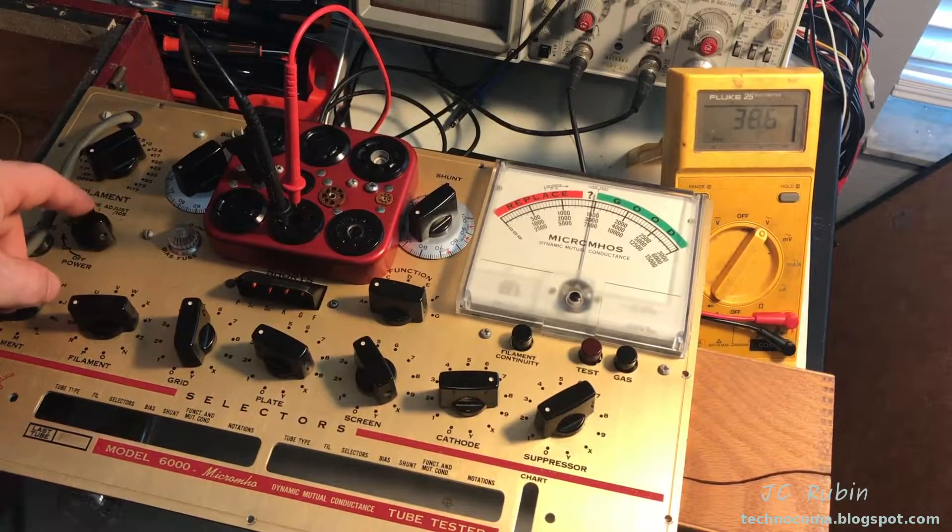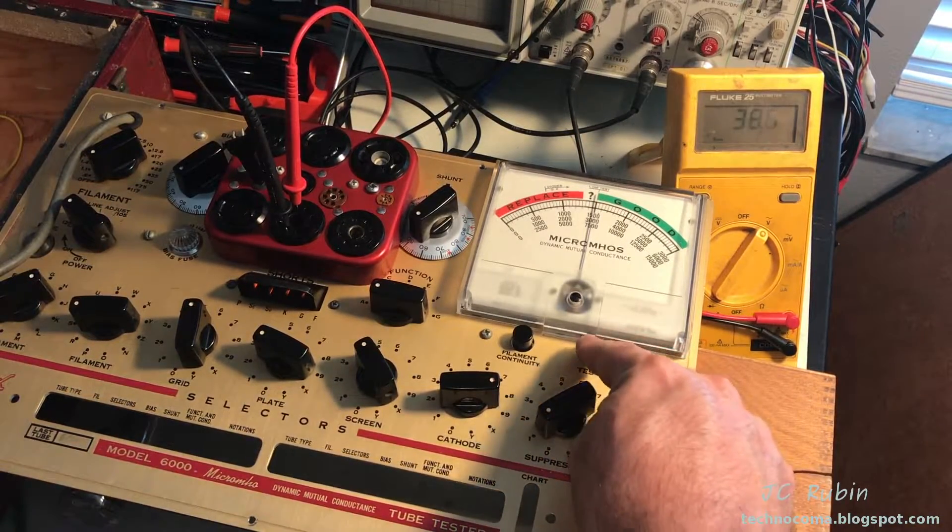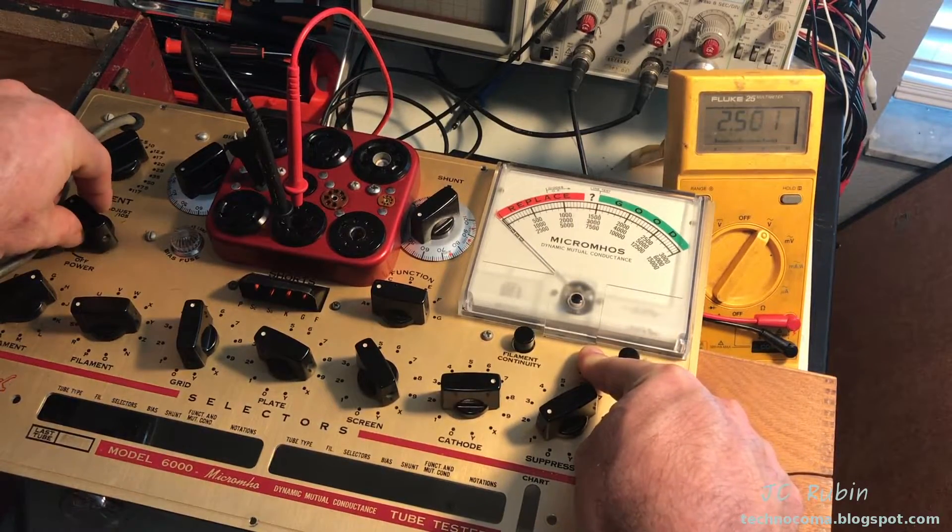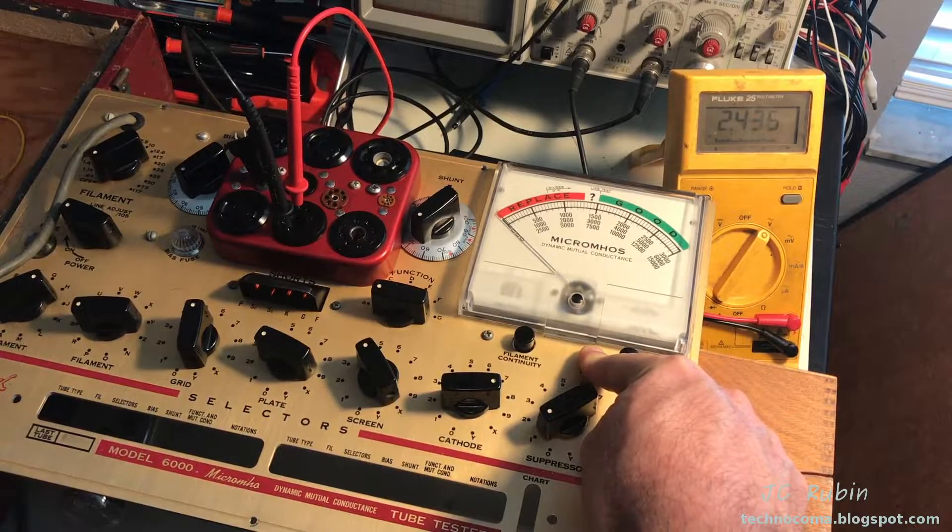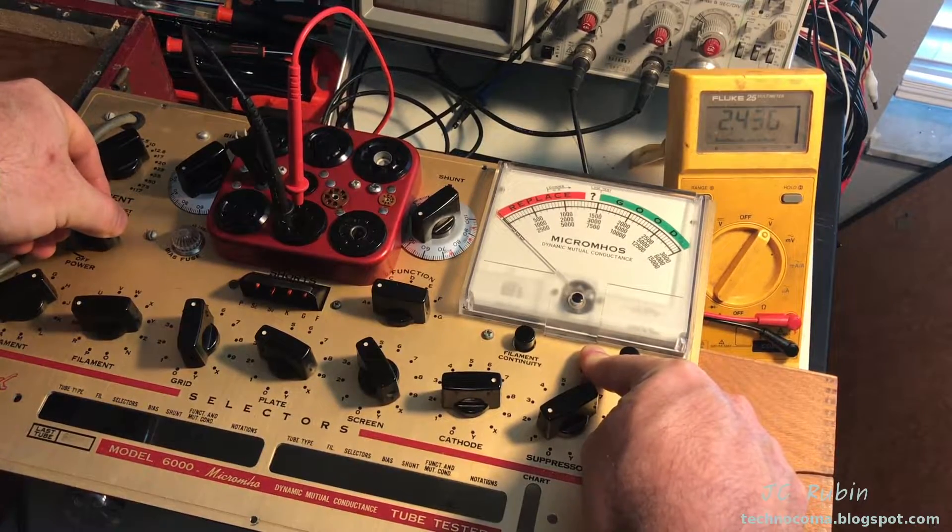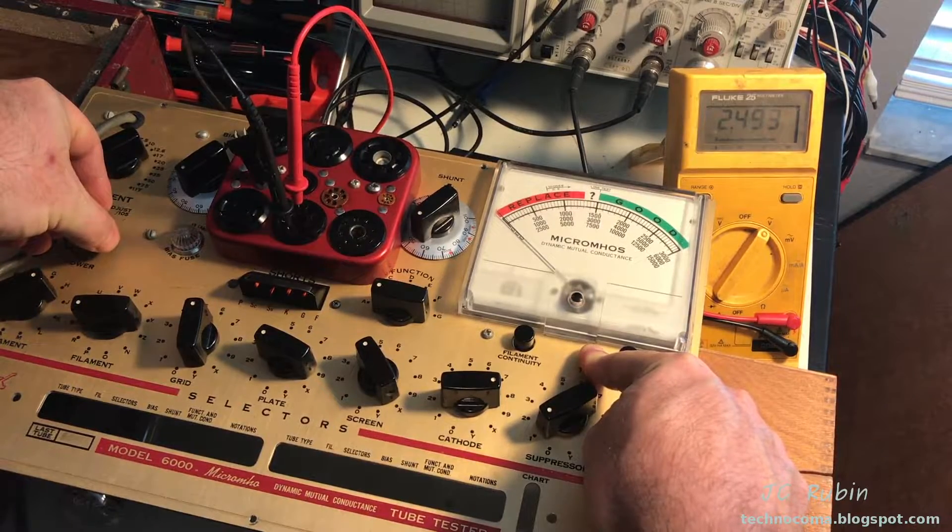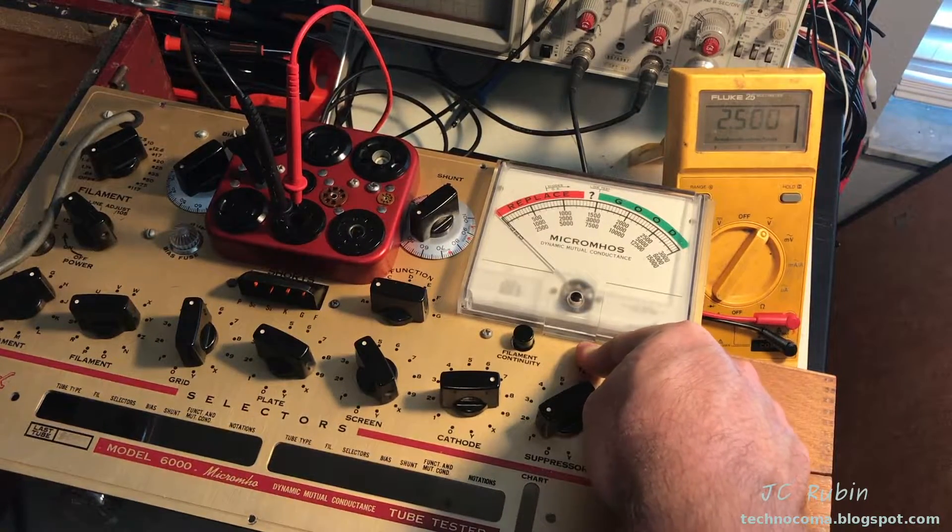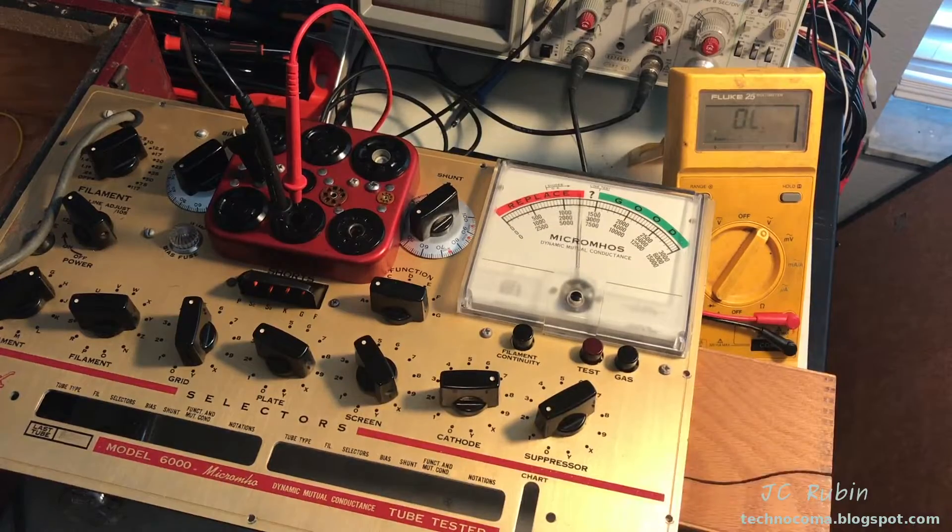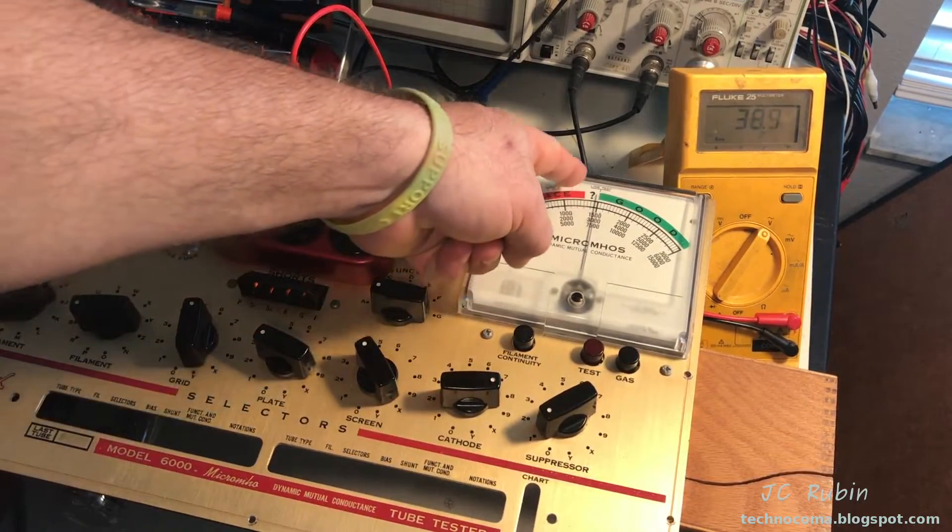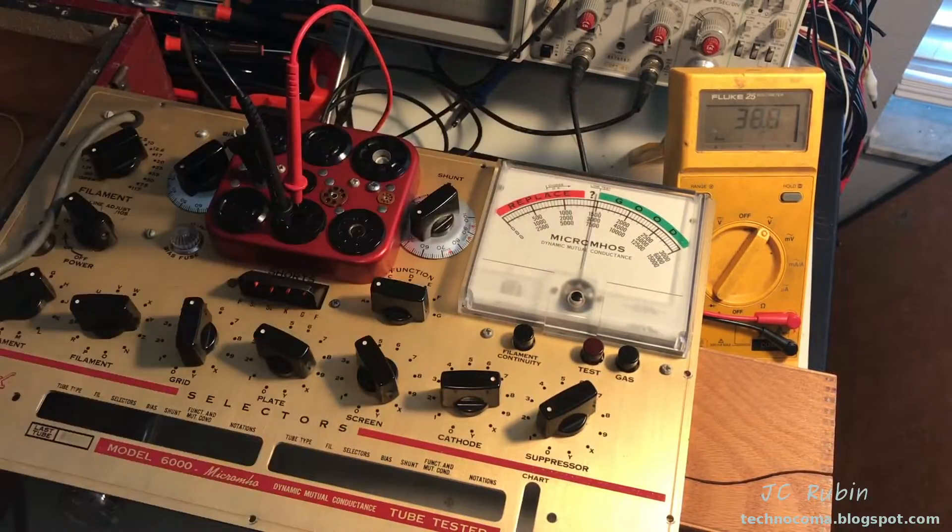That's what that pot is for. The 2.5 volts is coming from here. Watch, I'm going to hit test, see that 2.5. I'm going to turn the line and now it's 2.43. You're getting the 2.5 by adjusting the line. When I let go of test, it's that pot that makes the correlation between the 2.5 volts and putting it right there at line test.